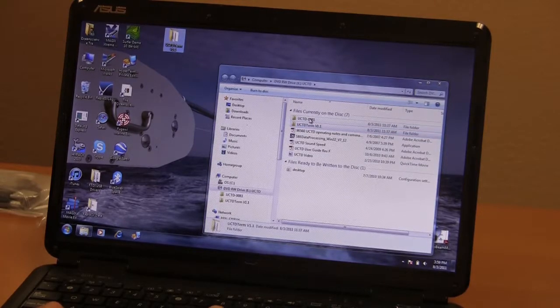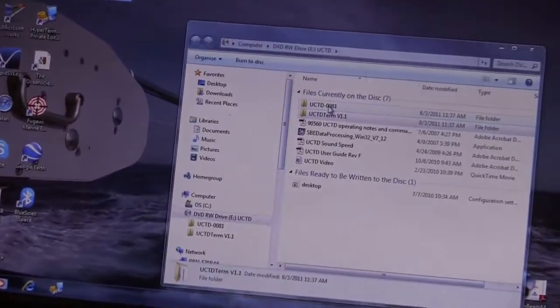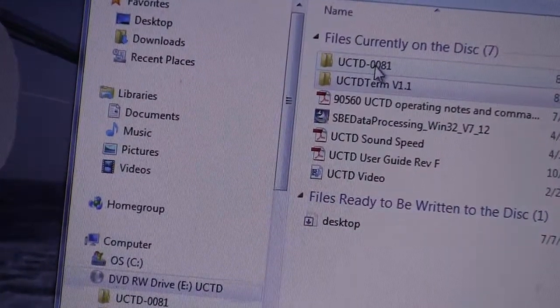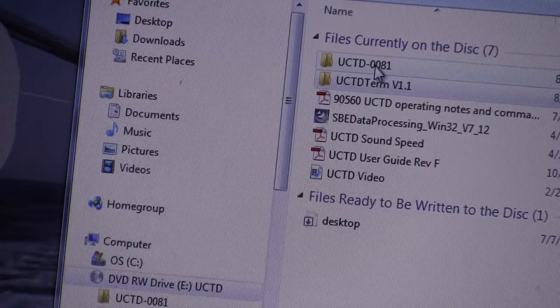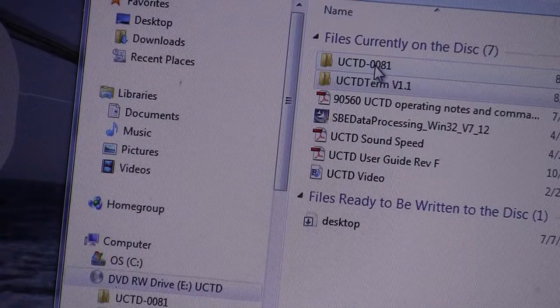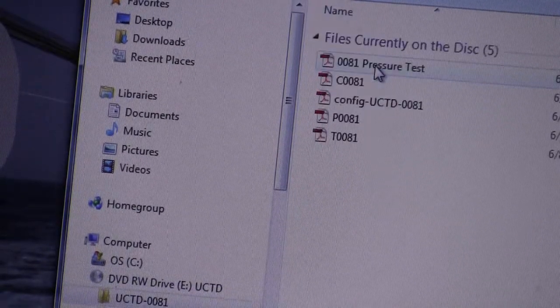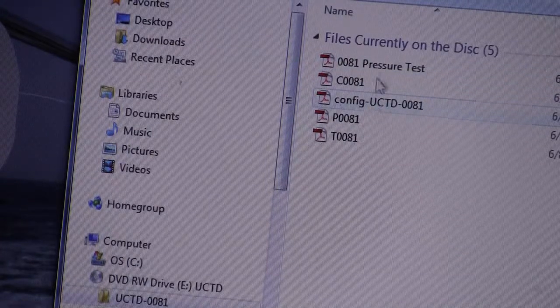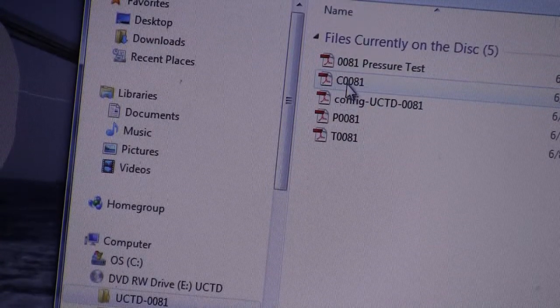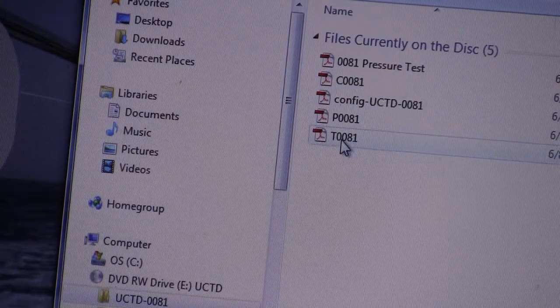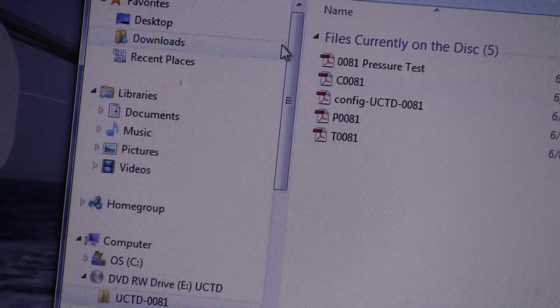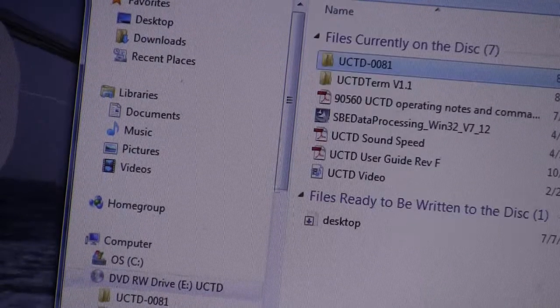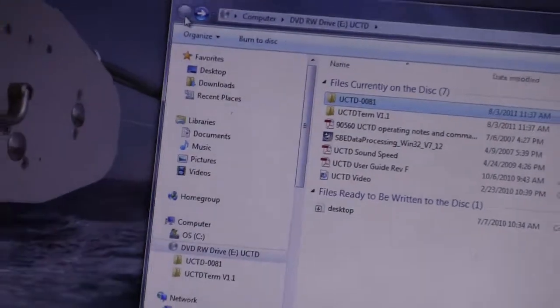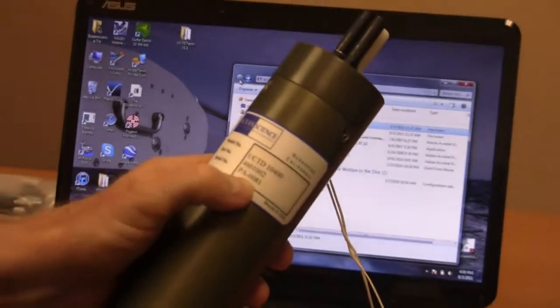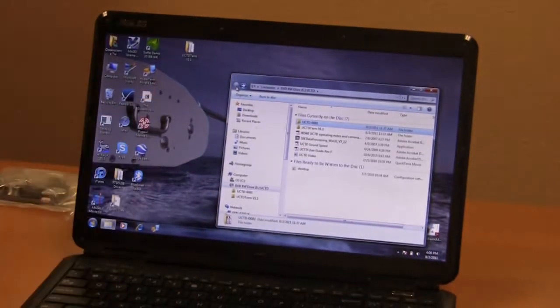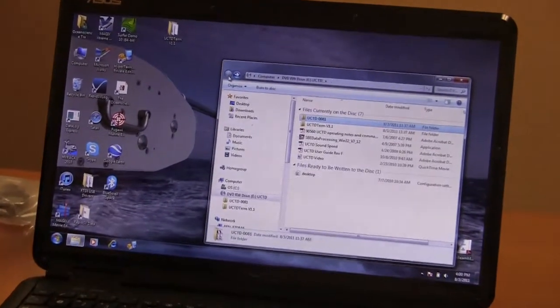There's also a directory that has a number behind it, and that's the serial number for the probe, and that contains all the calibration files and test reports from Seabird for that probe. So if we open that, you can see there's the pressure test, the configuration, and the calibration documentation for conductivity, pressure, and temperature. So that probe serial number is 81 and it'll be marked on the probe somewhere. Yes. You can see right here, that's probe assembly 0081. Okay. That matches the calibration information.